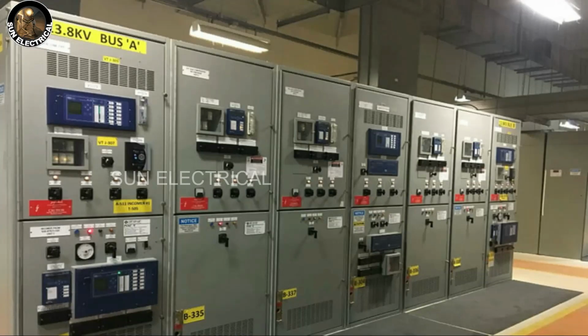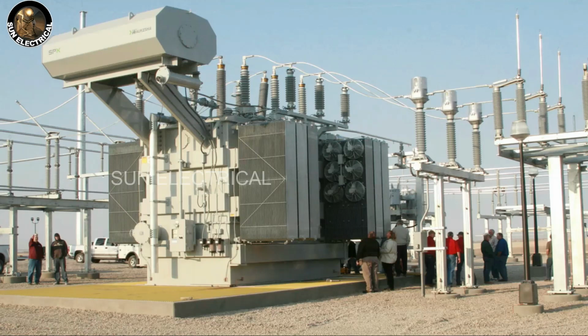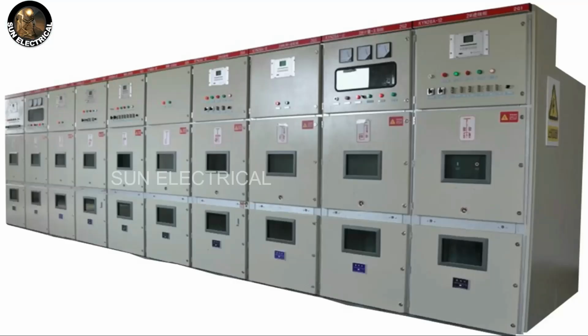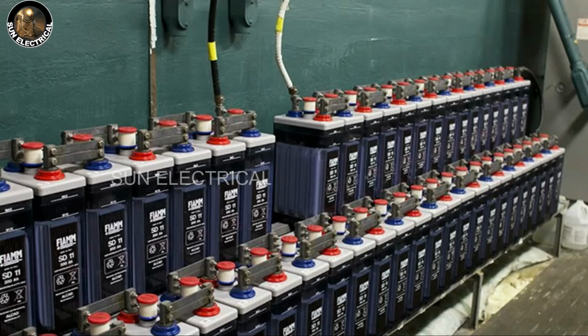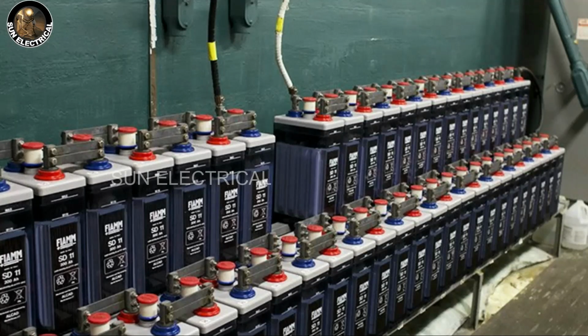The control circuit, that means the control panel or control system, for the switchgear system in every substation or industry consists of many circuit breakers, isolators and relays, which must be continuously on. If we use AC supply, which cannot be obtained from the battery, we cannot provide power supply to the control circuit during a power failure. If a power failure occurs in a substation or industry, all devices will stop working, then we cannot check the fault status, that means relay faults and breaker faults in control panels. So during a power failure also, we have to provide a continuous power supply to the control circuit or control panels, and we can provide continuous power supply only using batteries.